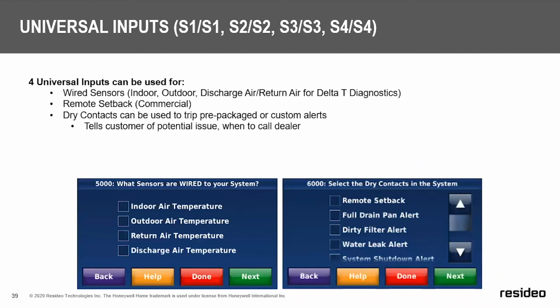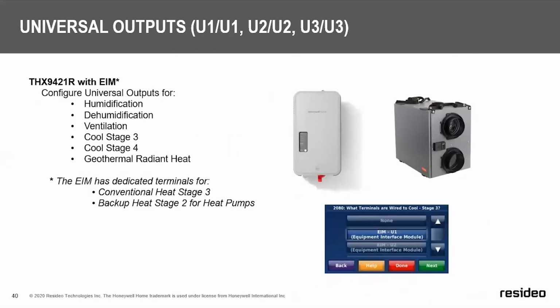Prestige IQ and Vision Pro, when using the equipment interface module, offers 4 S inputs, which can be used for wired sensors for indoor or outdoor temperature readings, discharge air temperature readings for diagnostics, or remote setback in commercial applications, or potentially for dry contact devices to be used for alerting, for example, a full drain pan alert or dirty air filter alert. The EIM module also can be used and configured for HUME, DEHUME, and ventilation, or additional stages of cooling, or geothermal radiant heat.